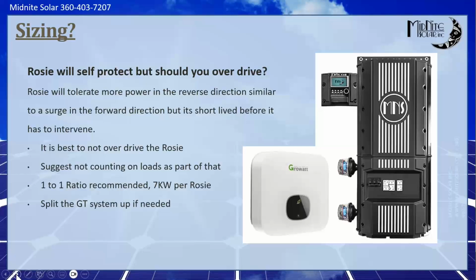And what I mean by that is, if you picture that Growatt on the left is 10 kilowatts, and it's back feeding the Rosie on the right, the loads come from between those two. So if the customer had 3 kilowatts of AC load on, the Rosie would only see 7 kilowatts. So it would never regulate and everything would be perfectly happy. But if the customer shuts off that 3 kilowatt load, all of a sudden the Rosie is going to see 10 kilowatts and the system's going to shut down and the customer is going to call you.